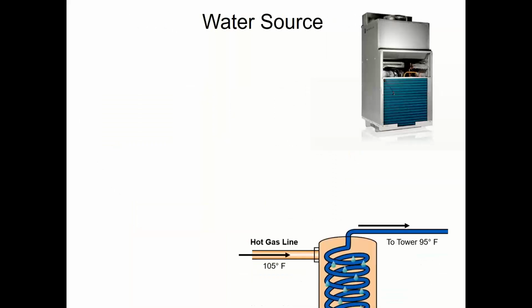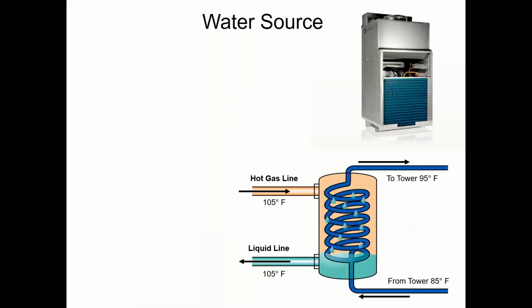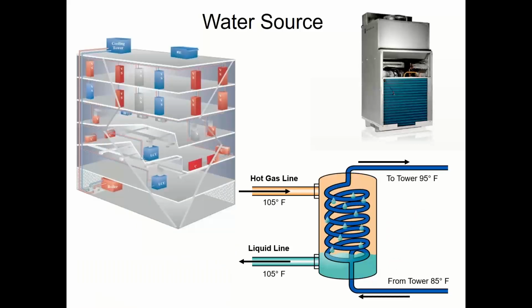If I do the water source stuff, I got multiple options there as well. This is going to typically be for larger buildings. You're not going to have typically 1 water source heat pump at, like, say, your house. You could, but it's not super effective. What I want to do is, so my refrigerant system, when it sends the hot gas from the compressor out to the condenser coil is not a coil sitting outside with air blowing across it. It's a water loop. The refrigerant goes and floods this tub, if you will, and then I run water through it. And the water picks up the heat.